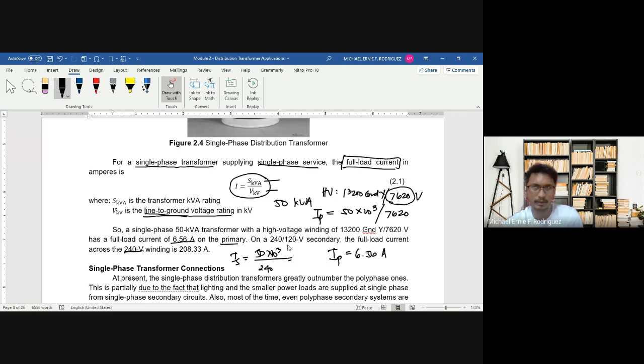On the secondary, we have the same 50 kVA rating, and the full load current is based on the 240 volt winding. So that is 50 kVA divided by 240 volts, which gives you 208.33 amperes. So if you notice, the current is smaller on the primary compared to the secondary. The primary current is small, which is why on the high voltage side the wire is small, only 6.56 amperes, unlike when the voltage steps down, the current becomes larger.